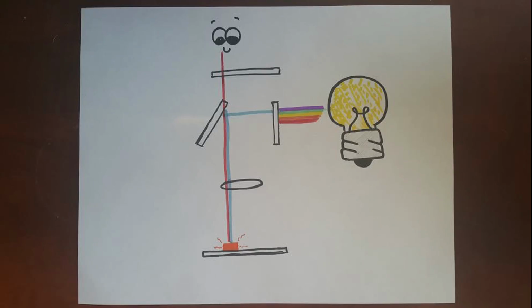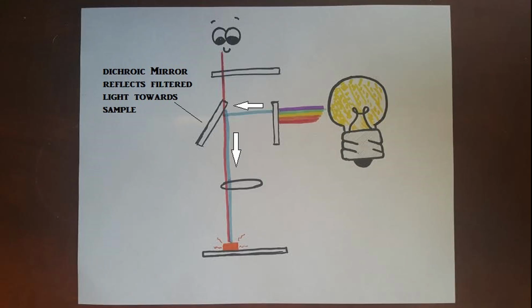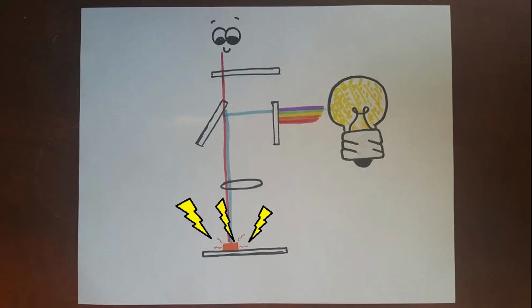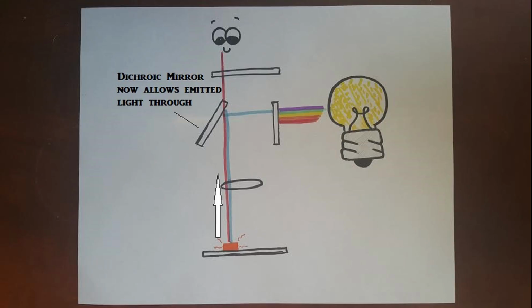Fluorescent microscopes have an amazing way of executing this complex process. First, light enters and is filtered to the optimum wavelength for the fluorophore stain being used. This occurs through an excitation filter. This light excites the fluorophores and they release light in return. The light emitted by the fluorophore electrons has a different wavelength than the light that excites them.